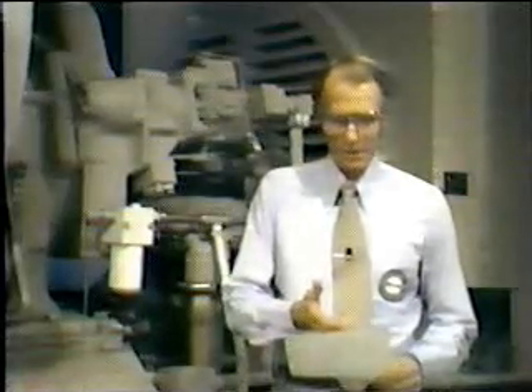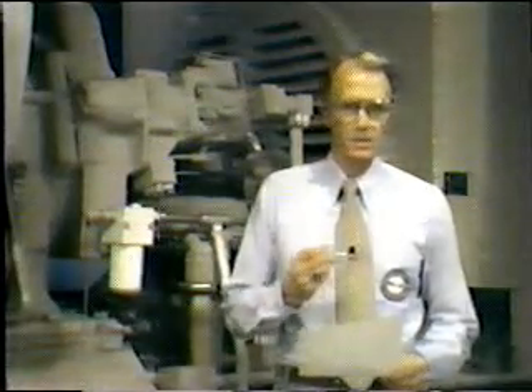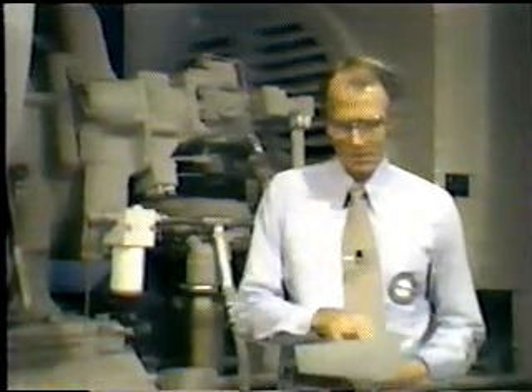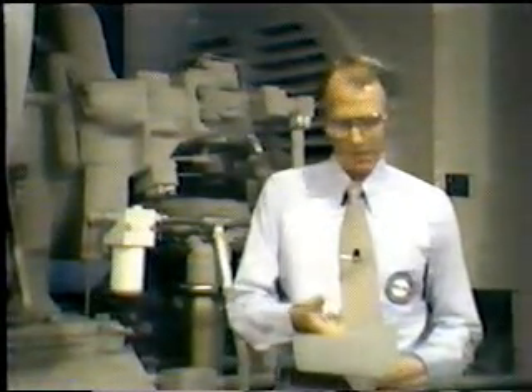CB502 is another main event and is placed in the far left-hand column. CB207 is a subsequent event occurring after the closing of CB502 and is indented to the right. To read the sequence of events during startup, you read down the page.